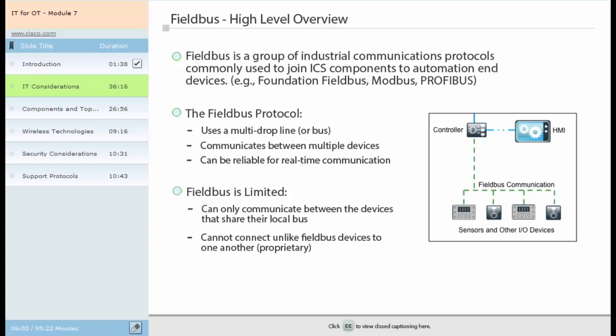Fieldbus is a group of industrial communications protocols commonly used to join IACS components, such as programmable logic controllers, to sensors, actuators, drives and other automation end devices. Some fieldbus examples include Foundation Fieldbus, ControlNet and PROFIBUS. Fieldbus is commonly used in manufacturing because of a multi-drop line optimizing cabling usage, communication between multiple devices on a shared bus, and possible reliability for real-time communication. However, fieldbus connections are limited. Unlike Ethernet, which allows all devices on the same network to communicate, fieldbus communication is transmitted only between the devices that share their local bus. Recognized fieldbus protocols are not interchangeable; connecting unlike fieldbus devices to one another is difficult and in some cases impossible because they are proprietary.